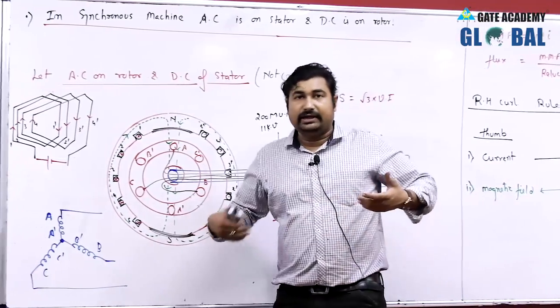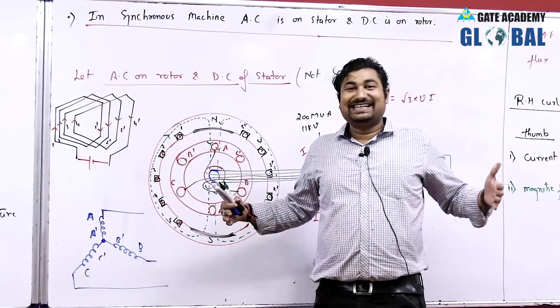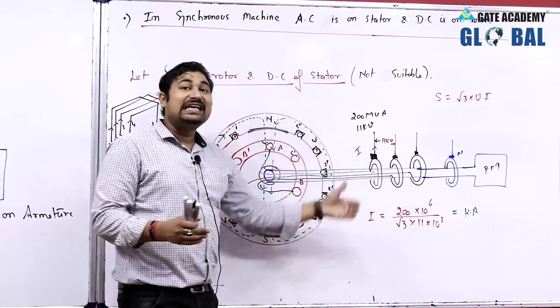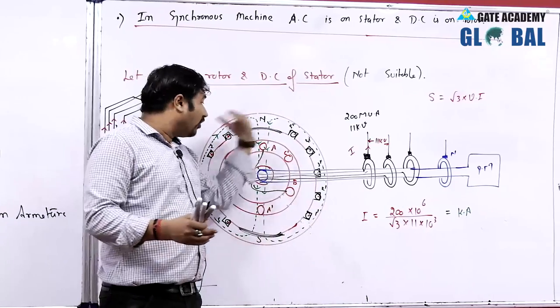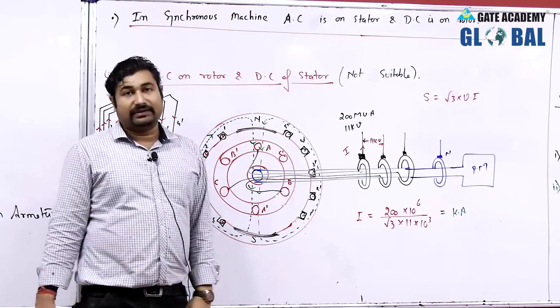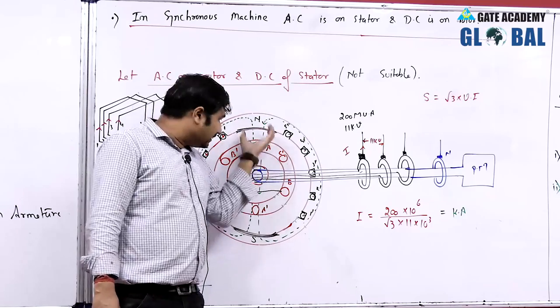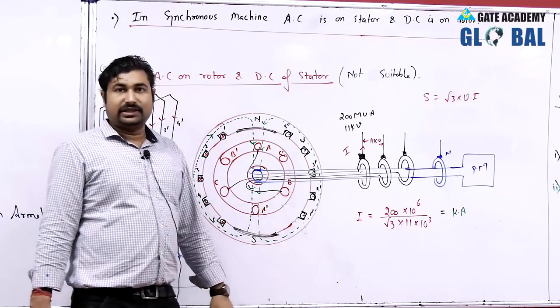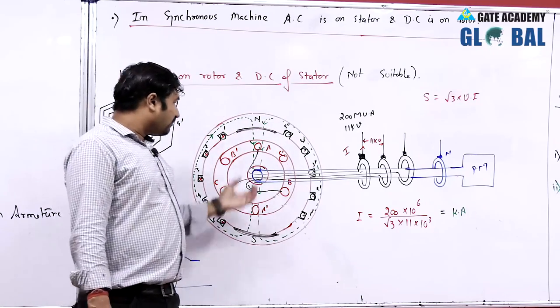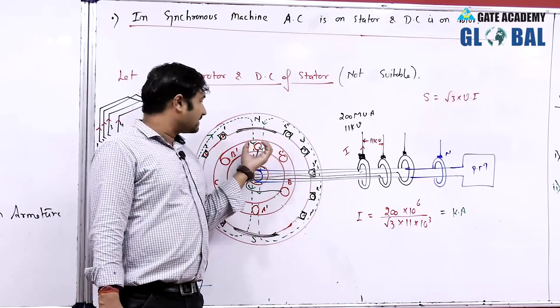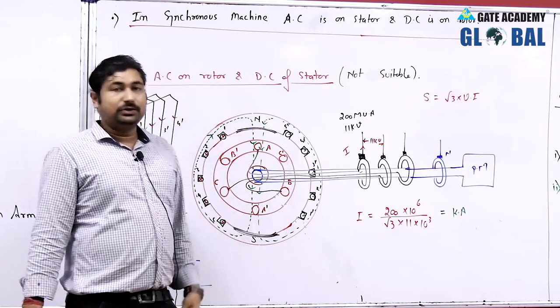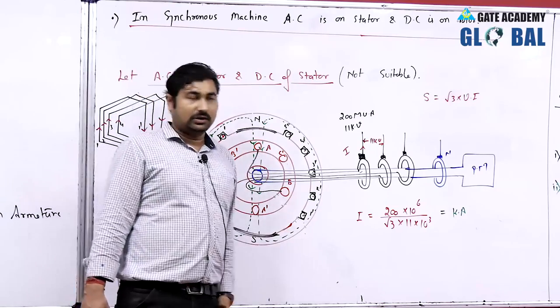If the current is in kilo-amperes, then the wire needed will be thicker than a person. If such a thick wire is rotated on the rotor, a very large centrifugal force acts on the wire and it becomes very difficult to hold that wire in the rotor body. This is the first problem: centrifugal force due to the large weight of the wire used in the rotor slots.